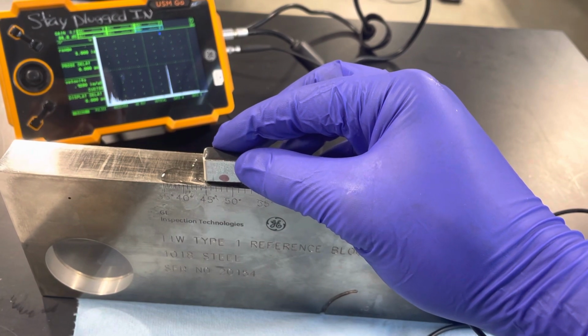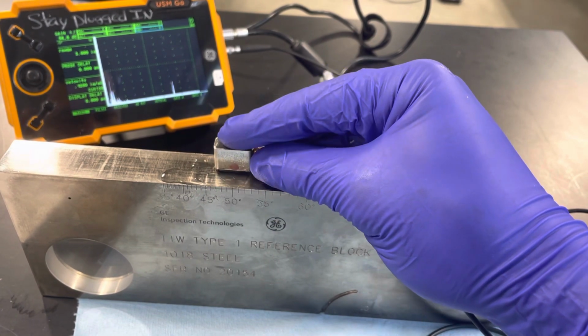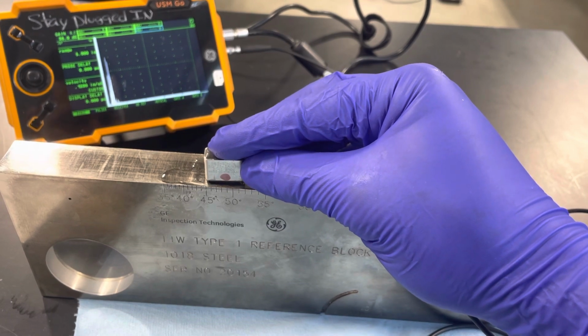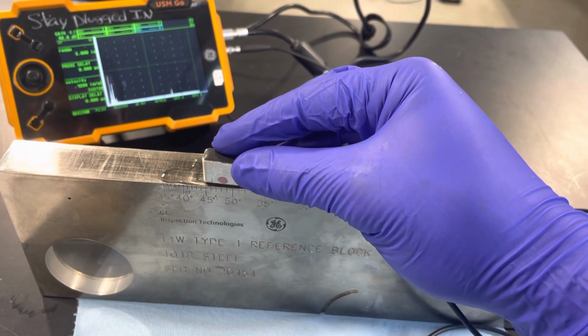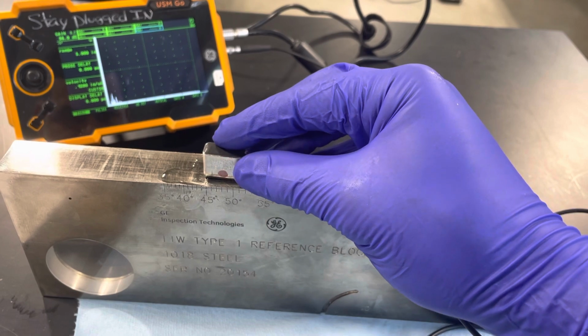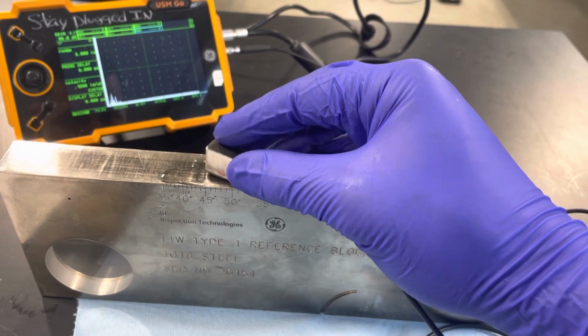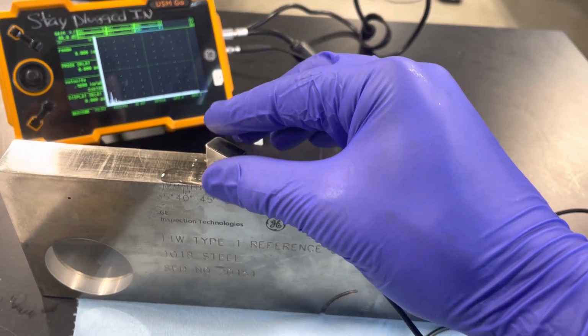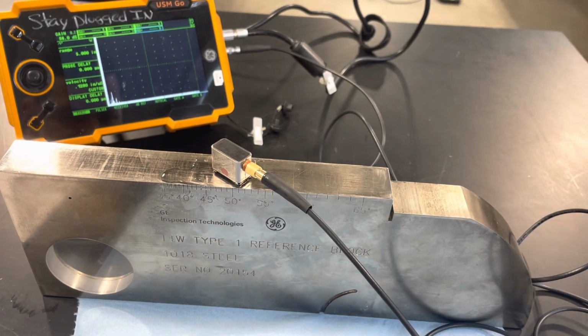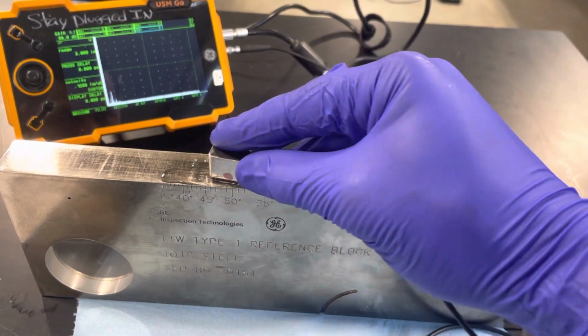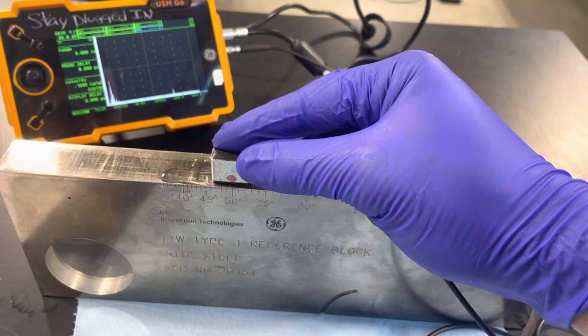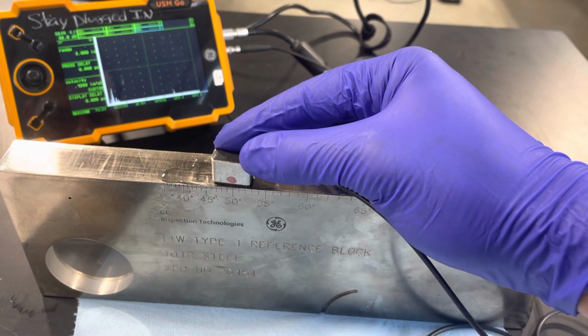Angle determination. We have a 5 megahertz 45 degree transducer, and we're using a type 1 IIW block. Procedure calls for a type 2 IIW block, but we have permission to use type 1 for this procedure.